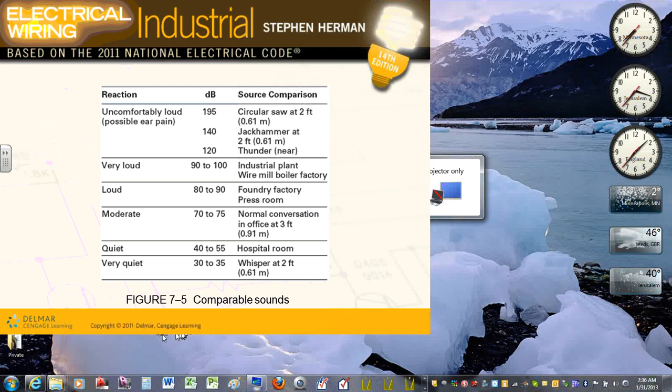In a hospital, quiet, right? So that will get you 40. Very quiet, 30 to 35. That's at 3 feet, though. If you're further, you have to project in order to reach the further people. So 30 to 35. So we probably would be right now, when I'm not talking, around what, 55? When everybody is here, maybe 50, 60. Okay, so these are your ambient noise levels. Who cares? When you design your system, you have to talk 15 decibels louder than this in order to be heard.